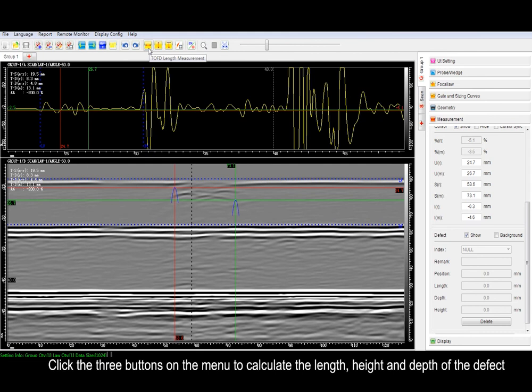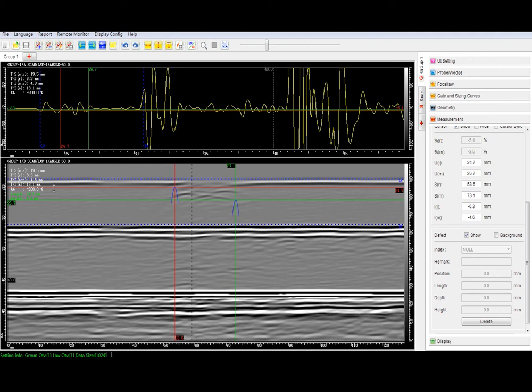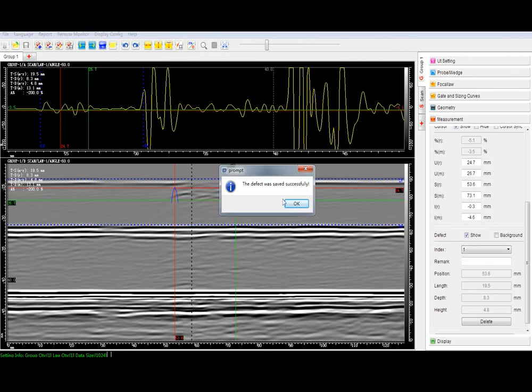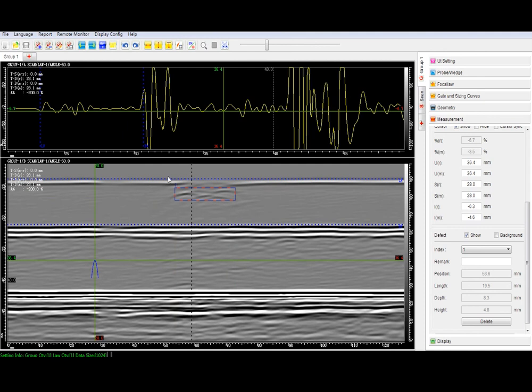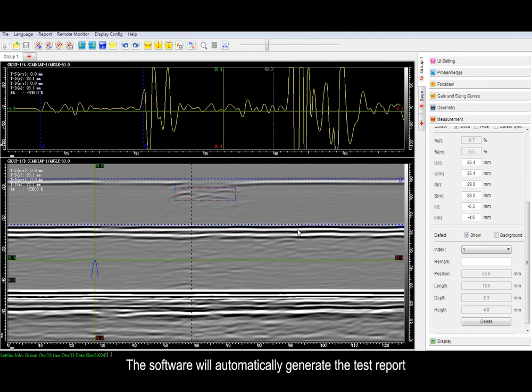Click the three buttons on the menu to calculate the length, height and depth of the defect. Save defect data. The software will automatically generate the test report.